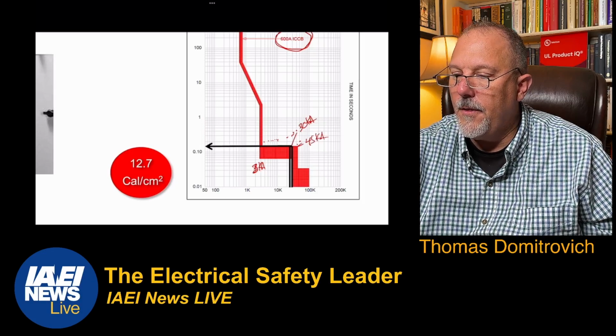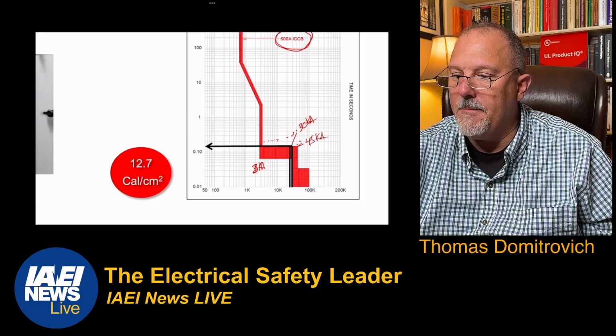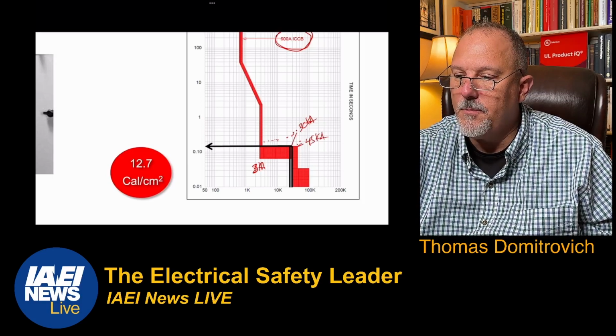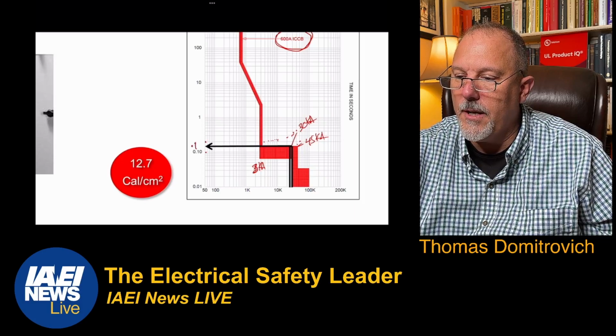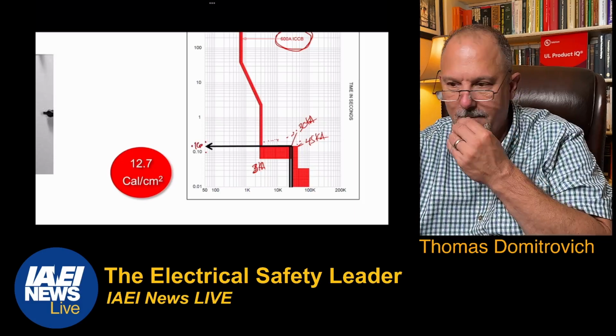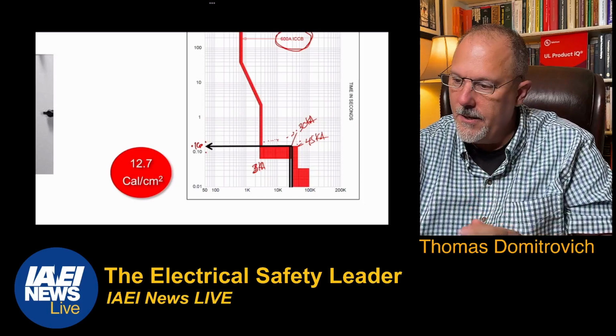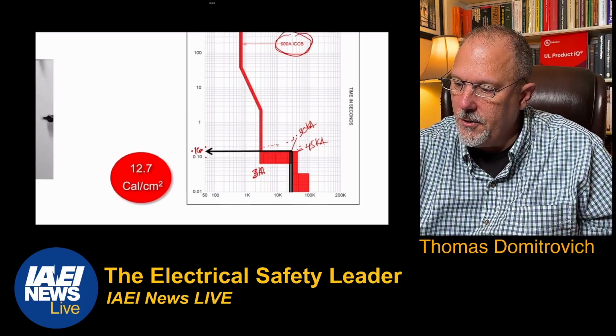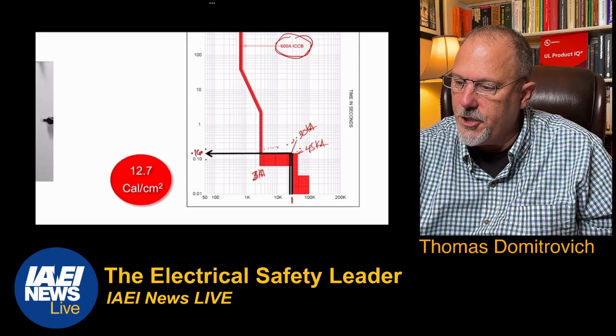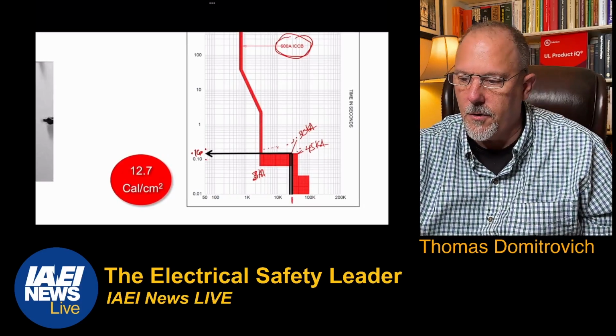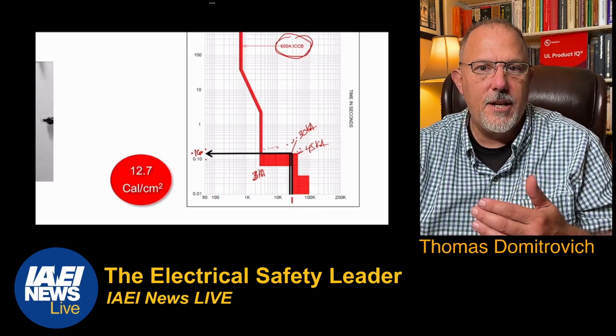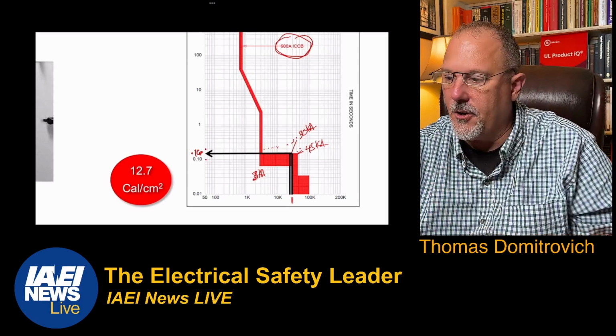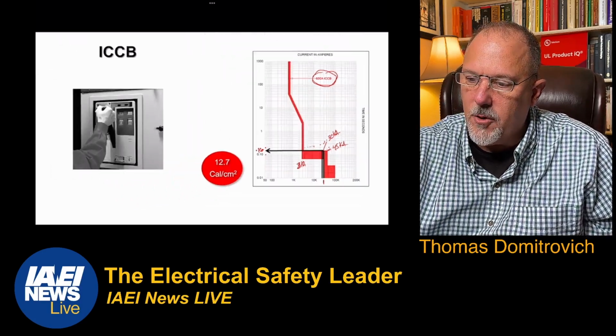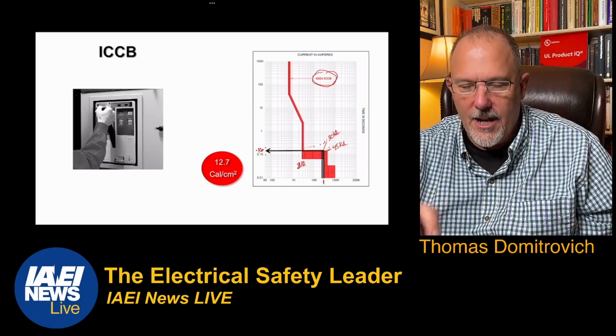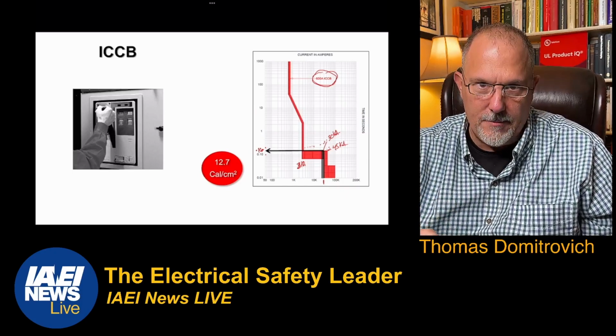From 3,000 to 45 kA, my clearing time is 0.1. This is 0.2. Say this is about 0.16, somewhere in there. So that's the difference, and that's how you read this curve. You know what your current is, you come to the clearing time, you come over, and that tells you how much time you're going to let any given current flow. So this is 12.7.